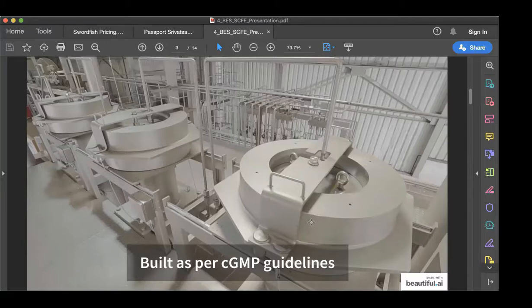We have a lot of redundant safety systems. That means if you have any overpressurization, your pumps will stop. You have automatic pressure safety relief valves. Even if that doesn't happen, nothing in the extractors can open until you vent the entire system out. So you have multiple levels of safety, including operators, supervisors, and administrators having different access levels to the system, so no one can come in and just increase the pressure or change a process parameter. All this complies with what GMP mandates — you need a recording of whatever change has happened, and no one can do anything unauthorized.